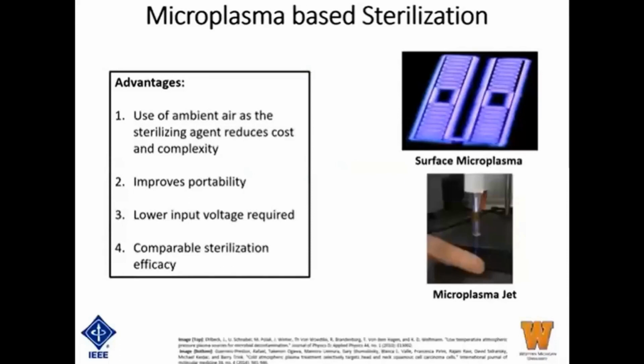The advantage of microplasma-based sterilization in ambient air is its use of ambient air as the sterilizing agent. This reduces costs significantly as there is no need for special chemical agents or chamber required. This improves its portability, and the devices are of smaller dimensions than traditional sterilization devices. The use of lower operating voltage is also a significant advantage, also reducing operational costs and bulkiness of the system.